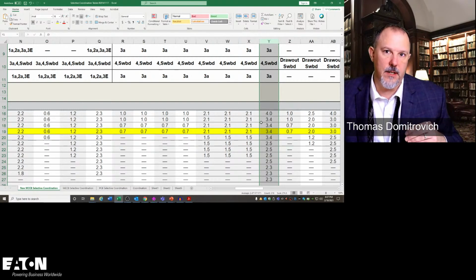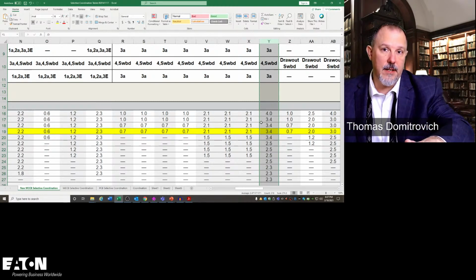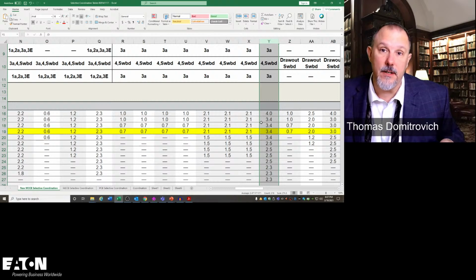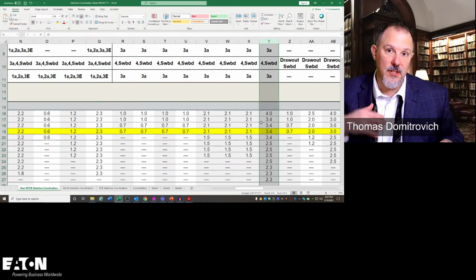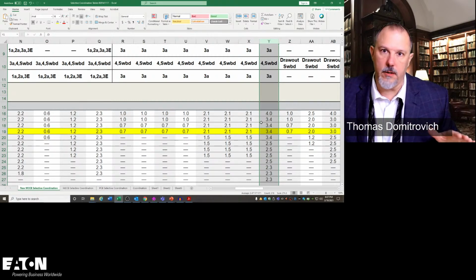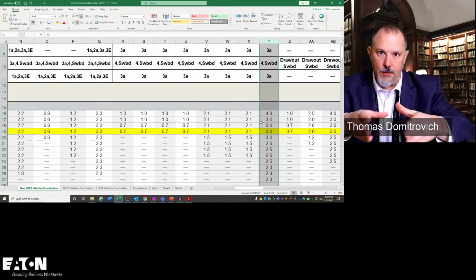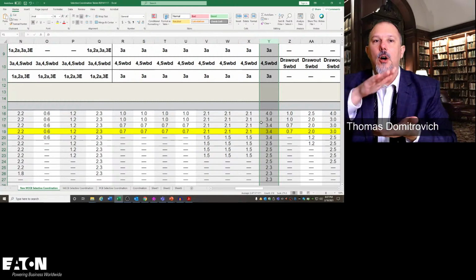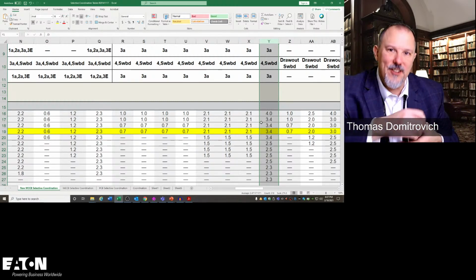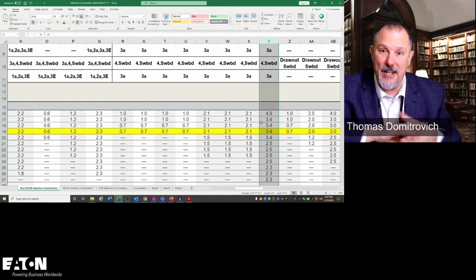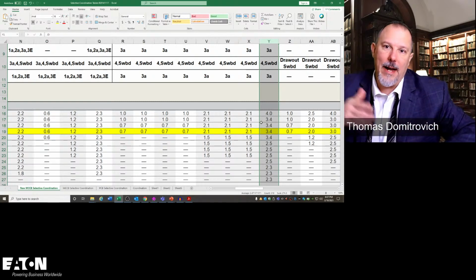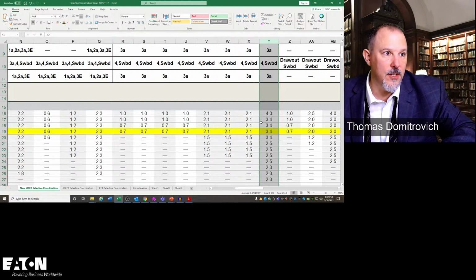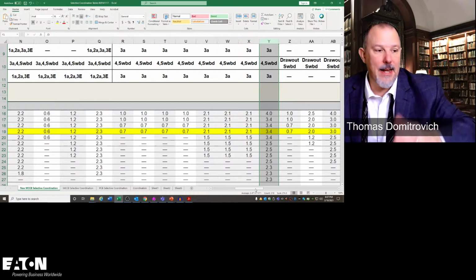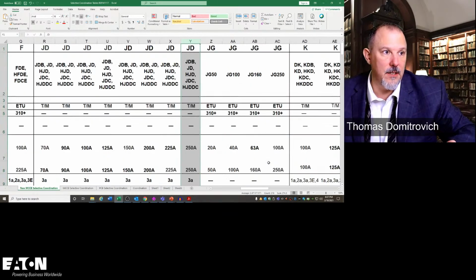So my perspective is, I'm sitting there saying, look, if you don't agree with a bolted fault current, if 517 healthcare lets you pick something different, my gut tells me you don't want to ignore fault current altogether. As power systems engineers, we need to say, what fault current do we want to selectively coordinate to or coordinate to? If it's not going to be the bolted fault current, why don't I want to go to the bolted fault current value? Because look, or why might I not? It's all about cost. It has nothing to do with anything other than cost.